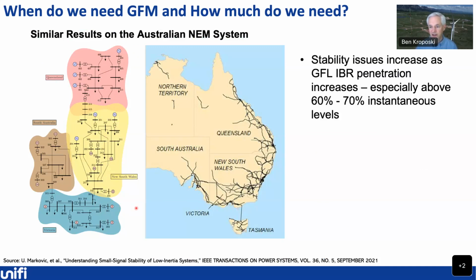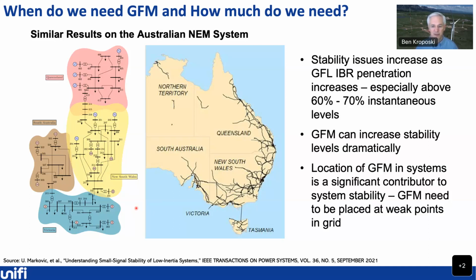And interestingly enough, basically came to the similar conclusions. Basically, above 60 to 70%, they started seeing much more stability issues. Grid forming technologies can actually help stabilize some of these particular issues. And again, the location of where the grid forming inverters were being deployed actually was a significant contributor to the stability of the overall system, and grid forming inverters should be placed at weak points in the grid. So there are some basic general rules that are starting to get developed now that we've been taking a look at these types of systems for a couple of years.